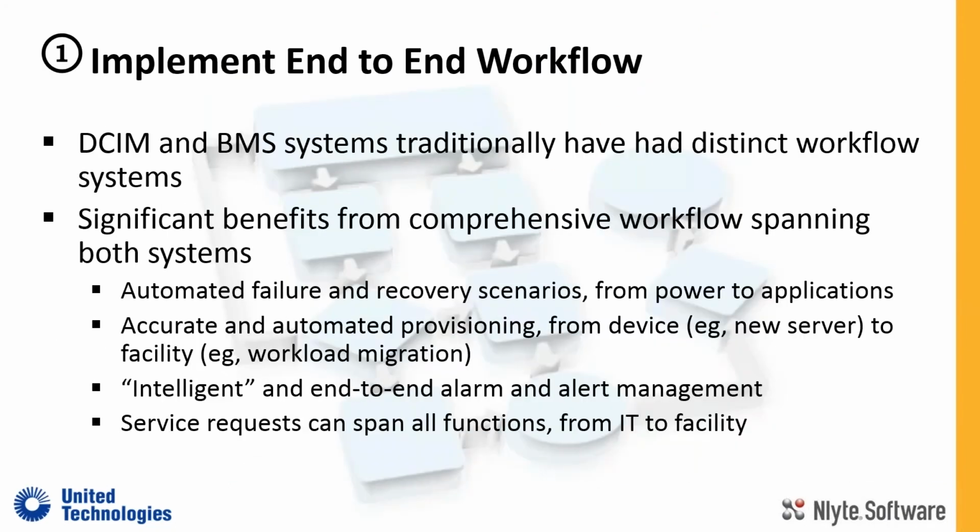So if we look then one level below, with those trends, with some of the specific feedback we've received from customers and the market itself, we just wanted to highlight what we find as perhaps the 5 most dominant areas that customers are investing in integrating their DCIM and their BMS systems together. And one of the first is implementing an end-to-end workflow. And the reason that this is so important is we all have experience in how we manage our systems. And traditionally, our DCIM environment and our BMS systems tended to be fiercely independent. Yet, they need to work together much, much better, because when we have this comprehensive workflow, we're able to implement automated failure. We're able to implement automated recovery.